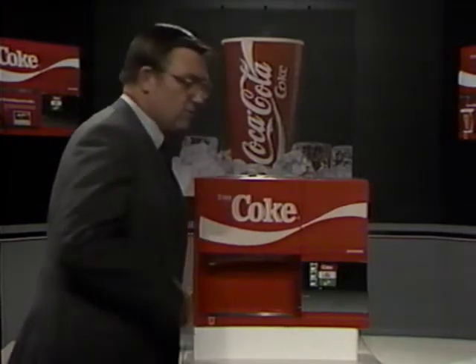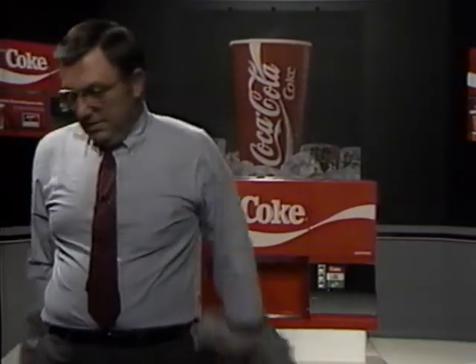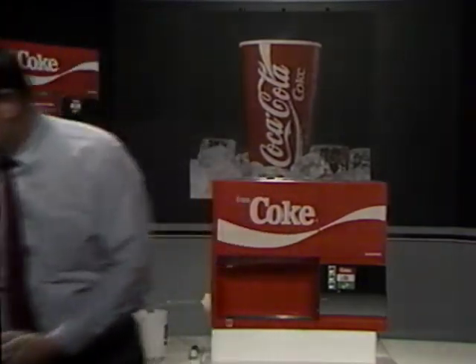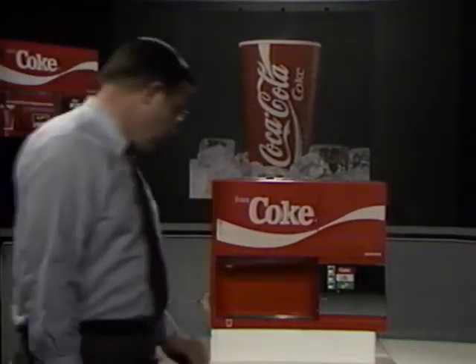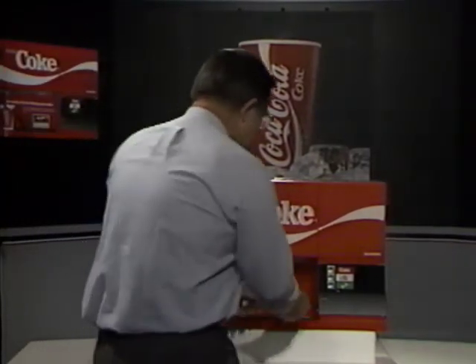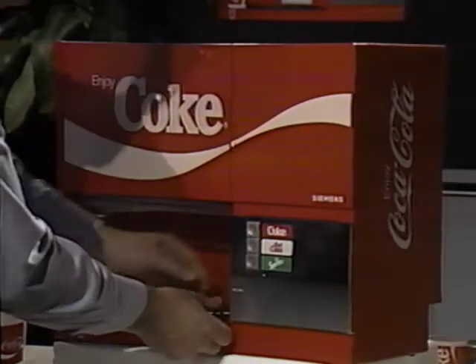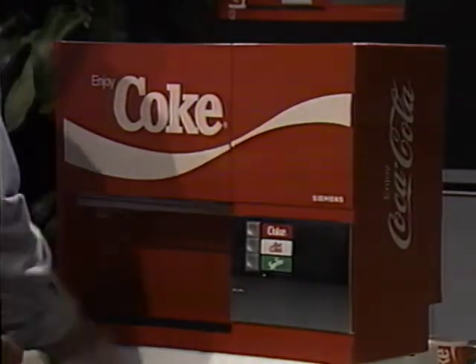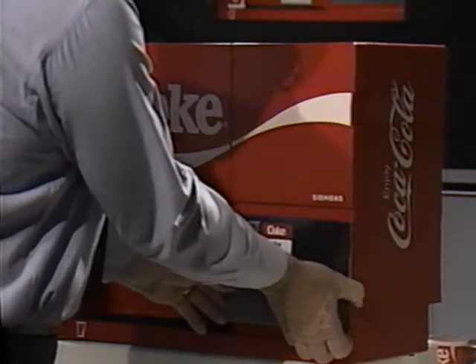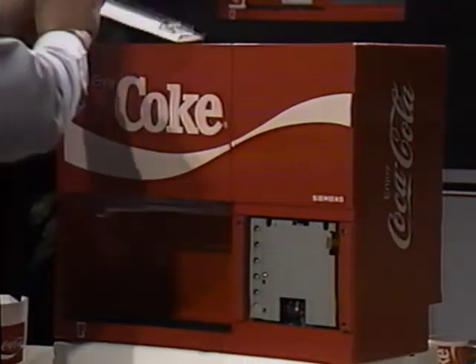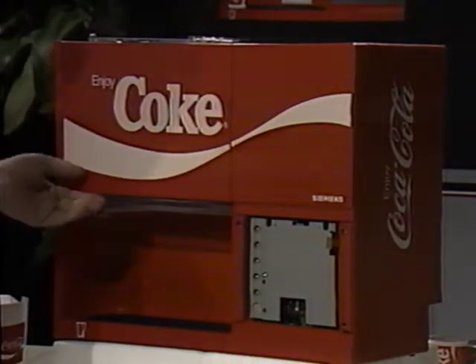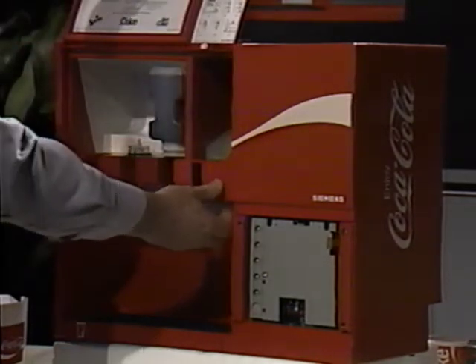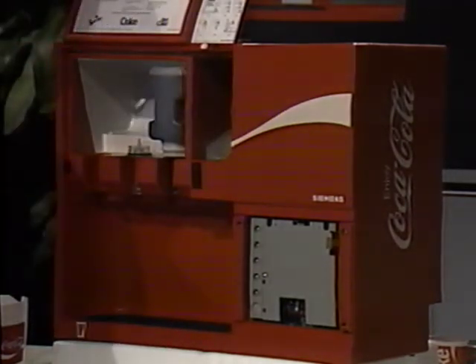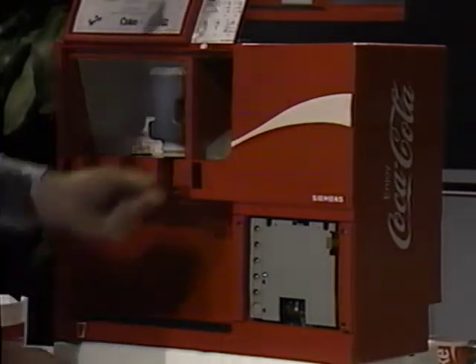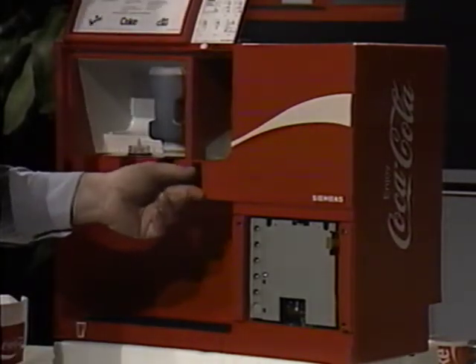The first thing you'll want to do is get the cover off of the ECM board. You do that by taking out the screw, prying up gently on the corner, and lifting the cover off. Then you want to take out your mixing channel, and then you want to put the machine in the diagnostic mode.